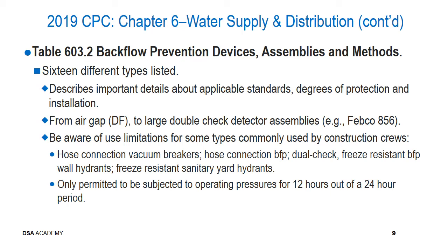It's important to make sure that these particular devices, these four, are only used for a maximum of 12 hours per 24-hour period. These devices cannot be installed for any more than 12 hours at a time, and that's specifically stipulated in the code. These types are not approved for continuous operation.